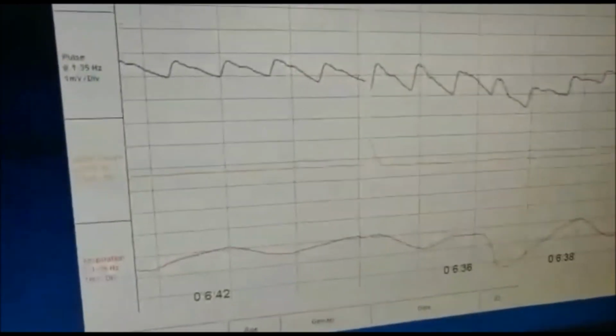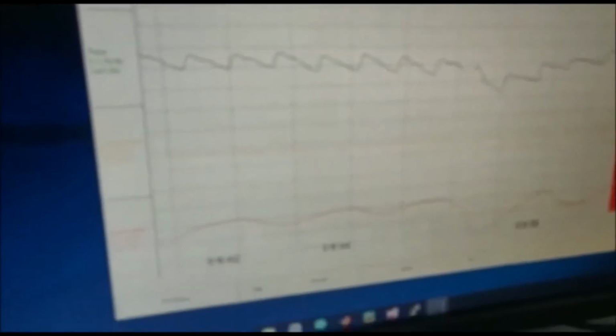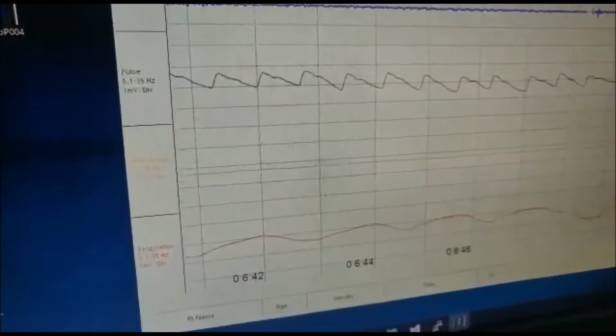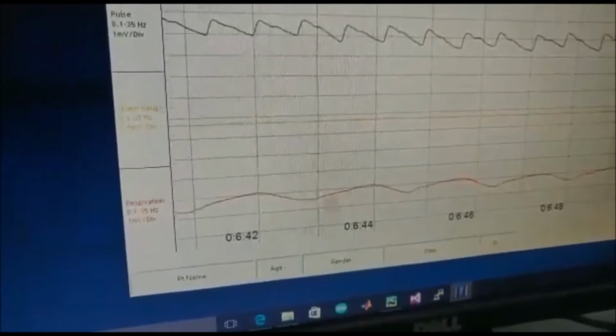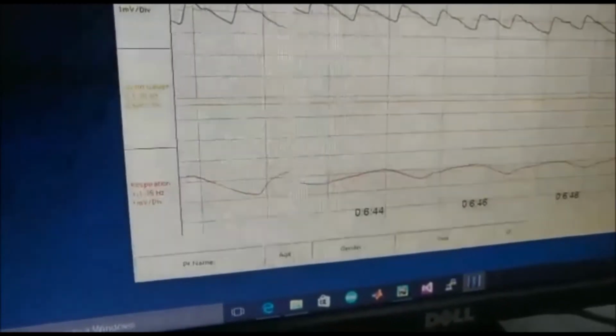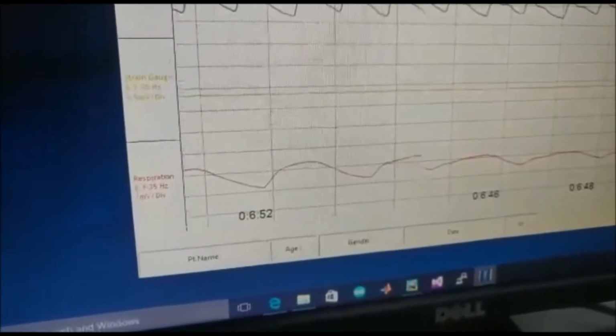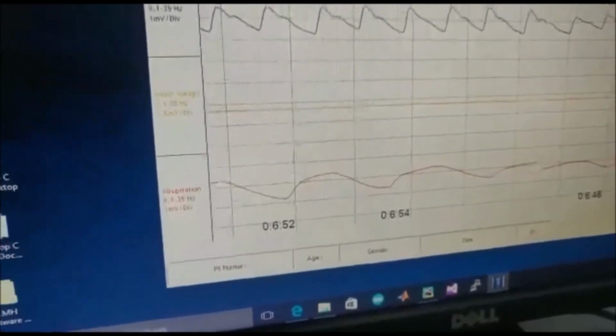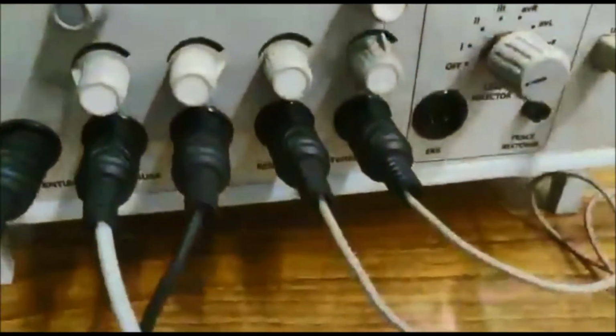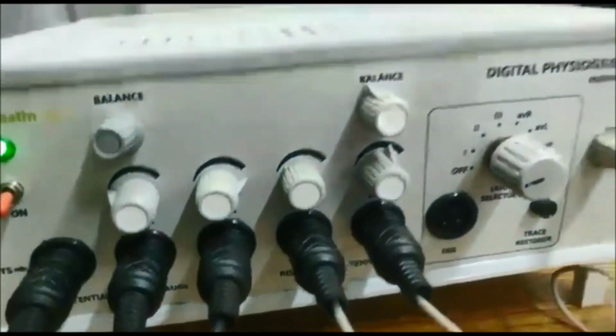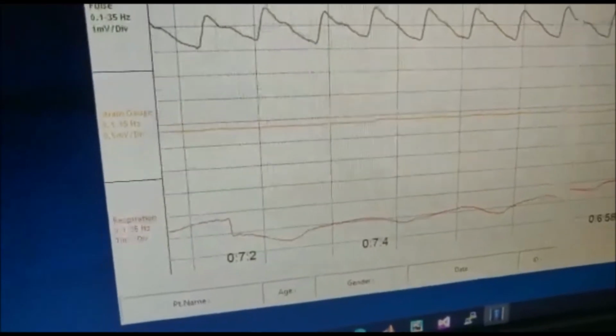And you can see in the software, each channel has its own filter range and sensitivity range. So suppose I look at the respiration channel, it is showing that the filter applied is 0.1 to 35 Hz and the sensitivity is 1 millivolt per division. You can also change the gain of the respiration from this knob. This is the external gain, and this 1 millivolt per division is the software gain.